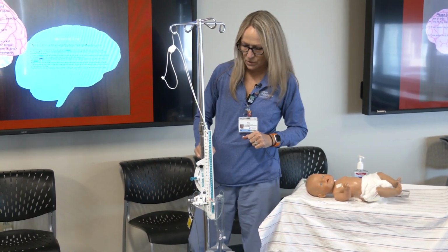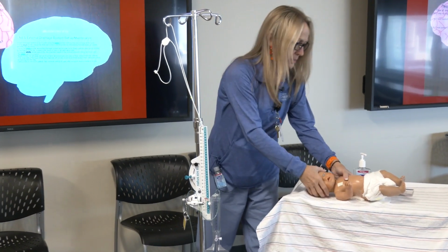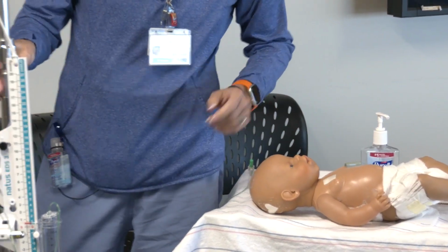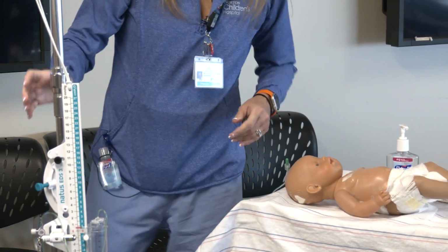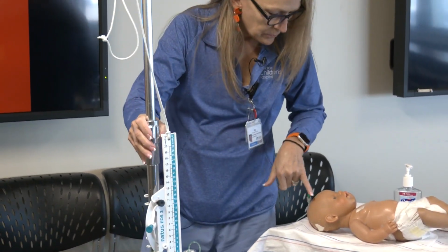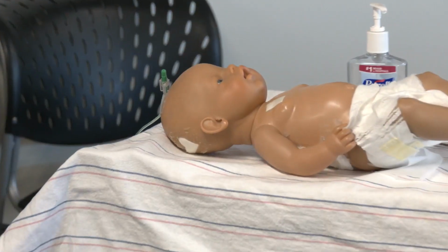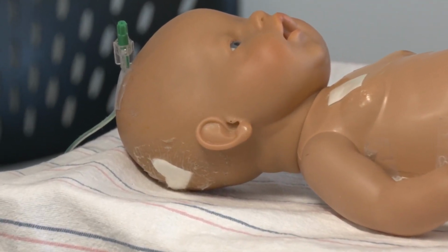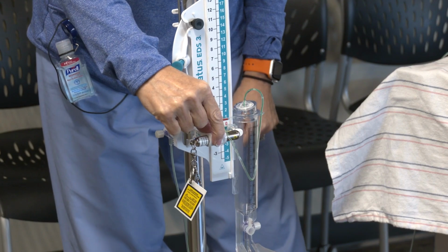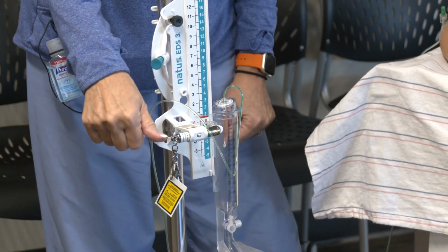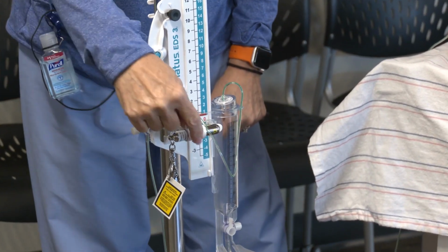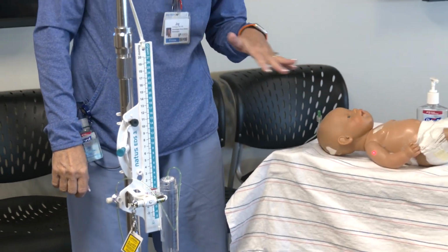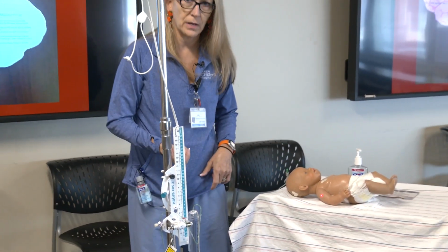And then the next thing we're going to do is zero to our patient. If you can remember where the order said we were going to zero it to, it is the tragus. I've put a little cheat dot there for you. It's this part of the ear, and I put a little dot there. So you push this button on the very front of it to turn it on. You used to twist it, but try to not twist it. Just push that button on. It goes off automatically, so you don't have to turn it off. But if it goes off on you and you're not done, you just turn it back on, okay?